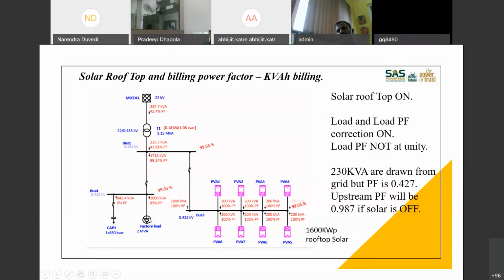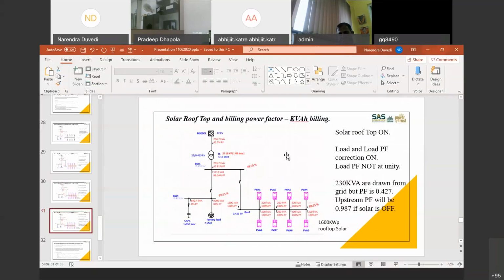That reactive power either has to come from your local source or it has to come from grid. There is no other source for that reactive power. Whereas for active power, now you have two sources. One source is grid, another source is your solar generation. So the moment you increase your solar generation, this active power taken from grid becomes less. And with less active power, if you take more reactive power, your power factor will be affected at this point. So this is what it is. I hope I have addressed it.